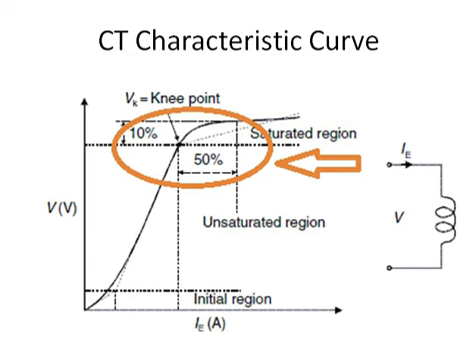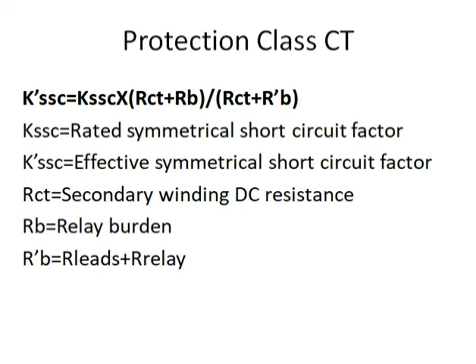This is IEC 60044, which defines the CT dimensioning and CT sizing criteria. As you can see from this formula: K_SSC_dash equals K_SSC multiplied by (Rct plus Rb) divided by (Rct plus Rb_dash), where K_SSC_dash is the effective symmetrical short-circuit factor.